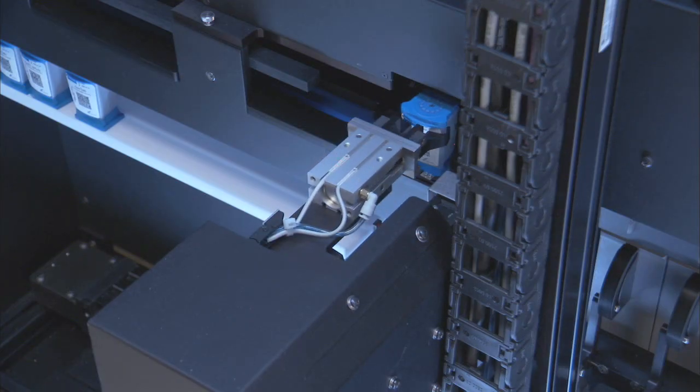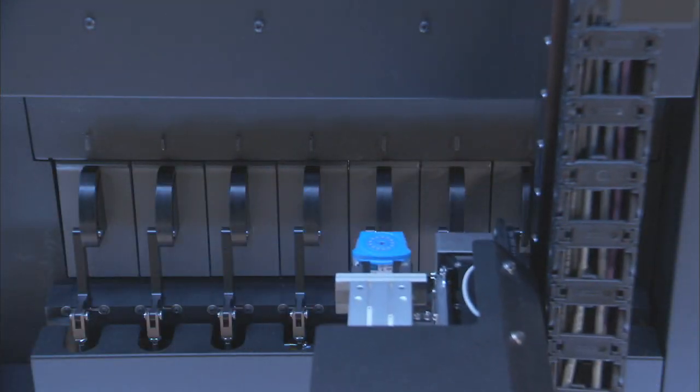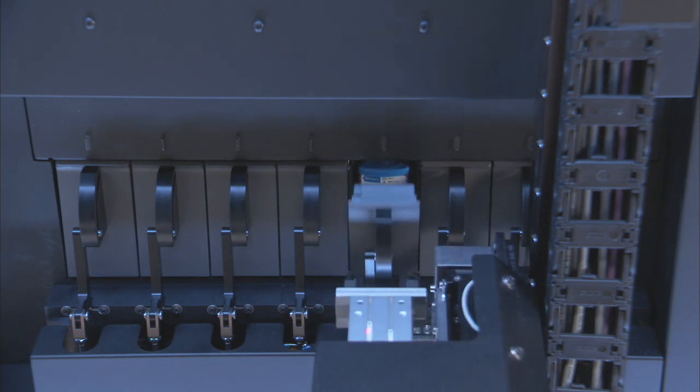Once verified, the Infinity picks up the cartridge and carries it to an available module. Infinity verifies that the sample identity matches an existing order. If an order did not exist for the cartridge, the GeneXpert software would alert you and the cartridge would be placed into the cartridge return area or shuttle.